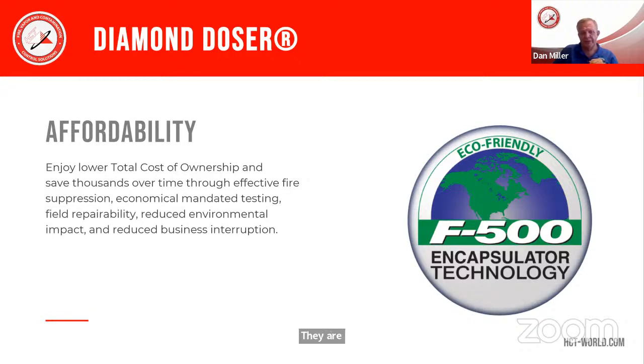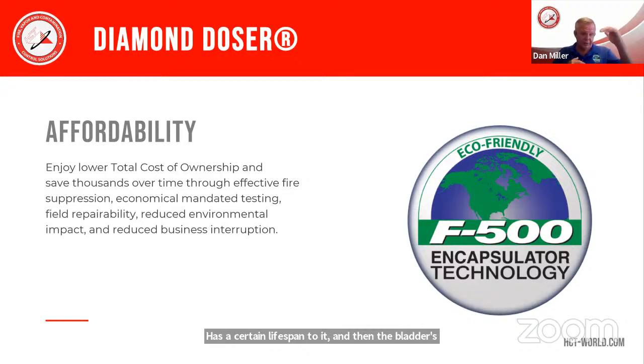A bladder tank has a certain lifespan to it, and then the bladder is probably going to go bad and it's going to need a lot of work. Then in annual testing, you'll lose a little bit of pressure and volume each time, so you've got to refill that, and you have some downtime for the system. You've also got the effluent that comes off of that you've got to deal with. With the diamond doser, you don't have to worry about any of that.